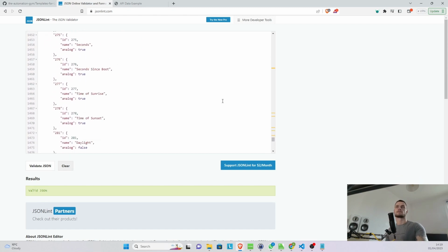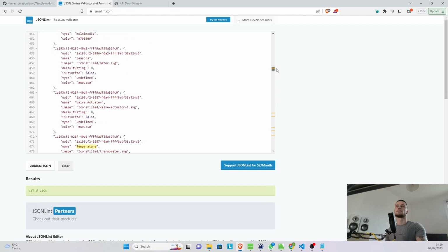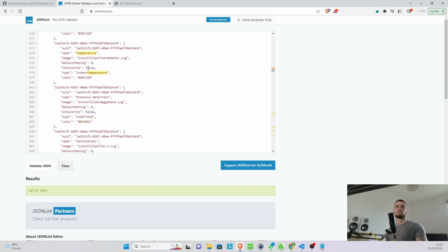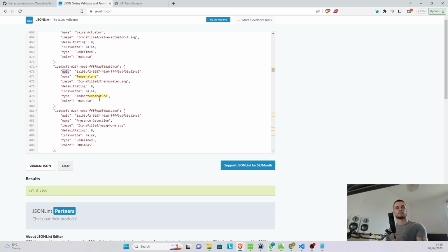So maybe the very first one we had, the one all the way up at the top, is the correct one. So this is the UUID, the unique identifier of that temperature sensor. And this is the long code that is associated with it. So the way to pull information from the Miniserver is that you can send a command and you can kind of request that data. You can request the state of the device and see, hey, what is actually going on?